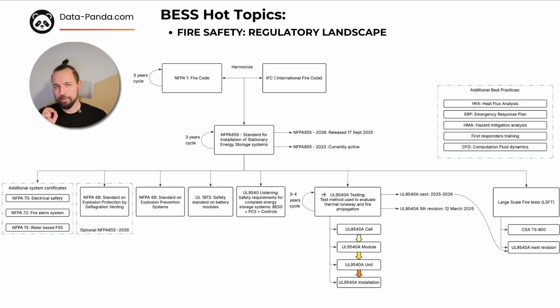And first I will start with a big nuance. Very often, UL 9540 and UL 9540A are confused with each other. But in real life, they are absolutely different standards, related to absolutely different tests. Even if they have almost the same names, their focus is absolutely different. UL 9540 is about electrical safety and threshold performance for safety. Remember, we looked into BMS thresholds and how all systems operate together. And UL 9540A is a test method for fire propagation. So you see, electrical safety and fire propagation are absolutely different things.